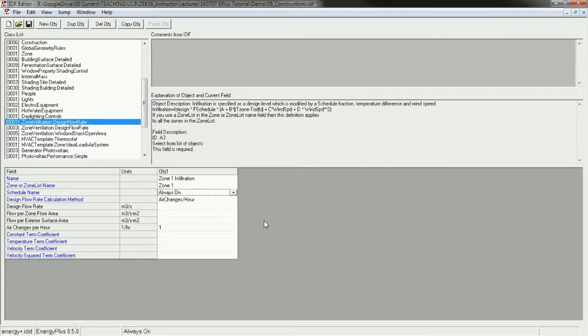It basically means that if you think of the total volume of space, that is equal to one air change. So that if all of the air is replaced, that is an air change. So how often does that air change happen? That is a measure of volumetric airflow. And so what infiltration is looking at is through all the cracks and leaks and little places where air can come and go, how often is the interior volume of air replaced?